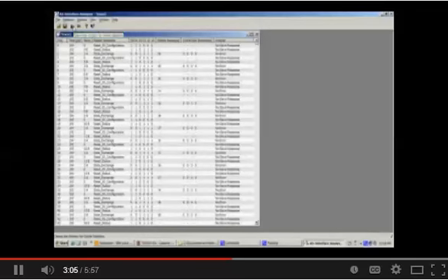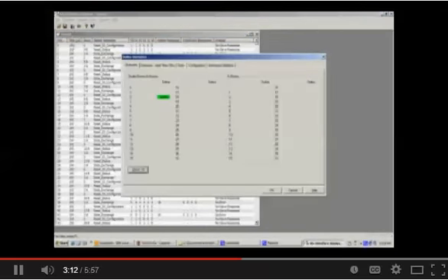You can also go live with this by clicking on this button right here, which opens the windows for online statistics. And if you click on that, you will see that I've actually got just one node here, node 2 on the network. I can go to the overview, hold time here 50 seconds, go to the data window here. I can actually turn on and off a sensor here and see that particular, on node 2 I've got a proximity sensor connected right here, and if I turn that prox on and off at the slave, you'll actually see that message coming back this way on this screen as well.